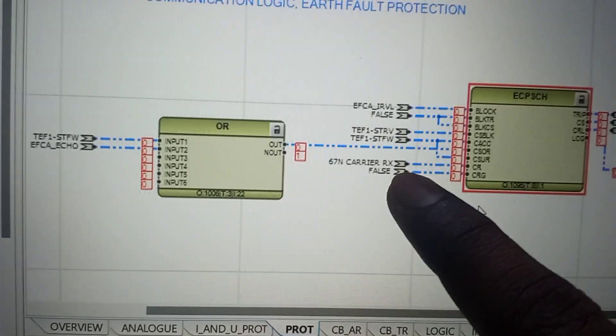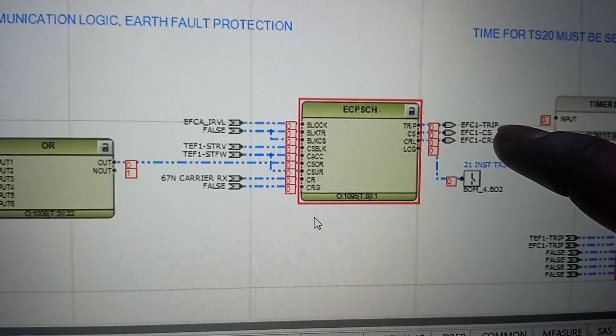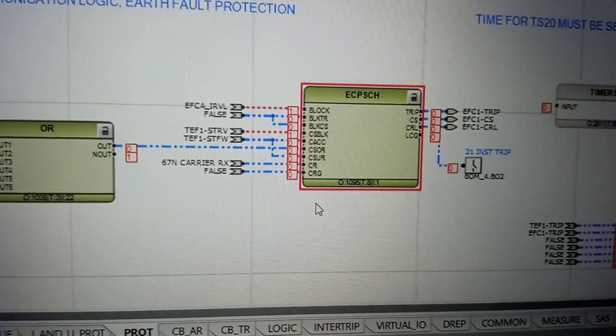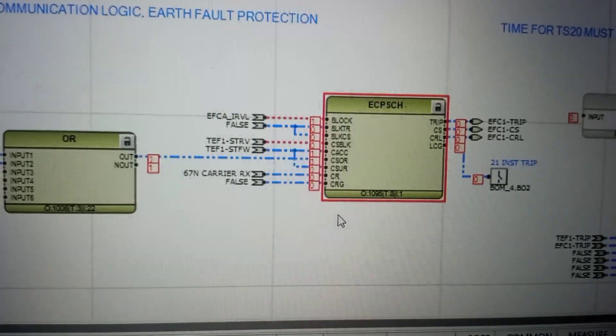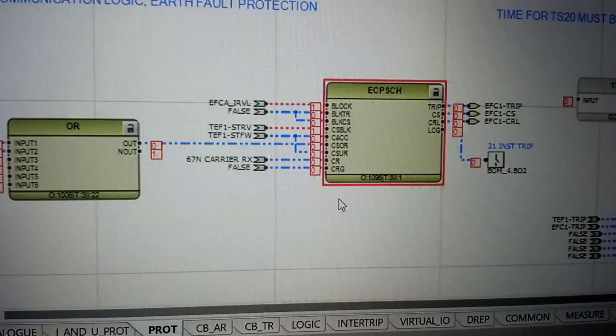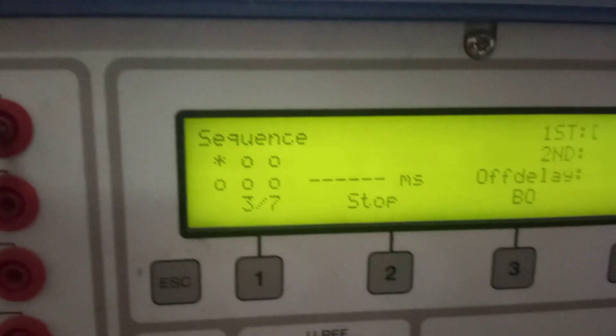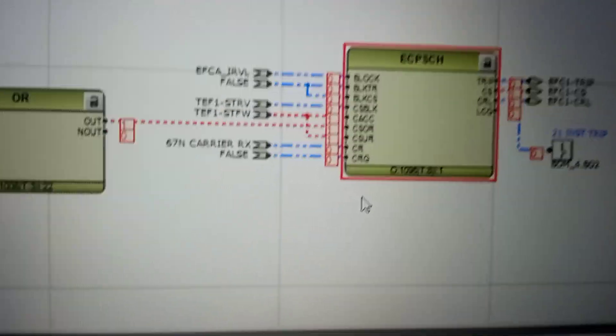You can see: DEF reverse, this is the forward step, and the carrier receiver — DEF forward. The communication trip output is also shown. Without carrier receiver, the first step is reverse and blocking. Then it comes forward also. There is no trip because it is blocked by the current reversal blocking scheme.